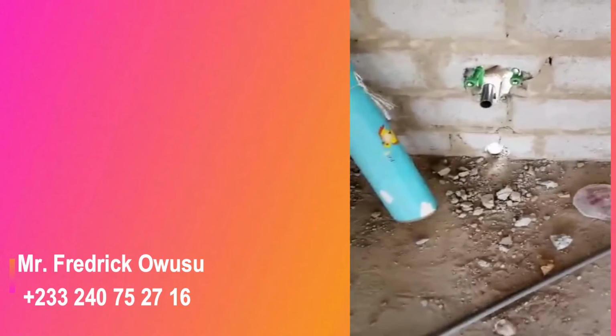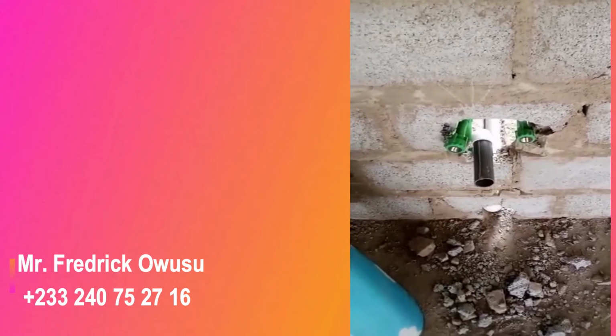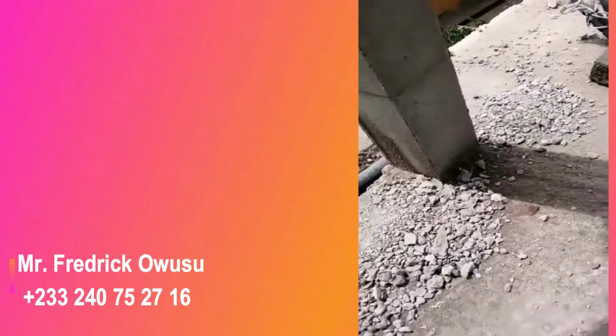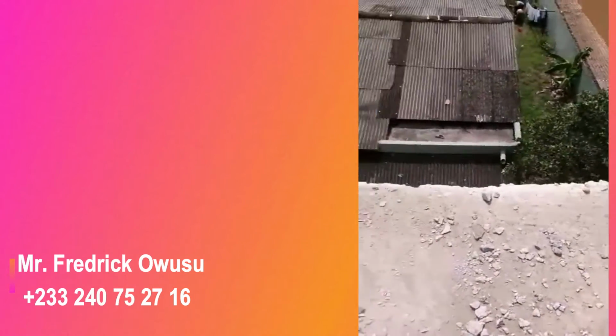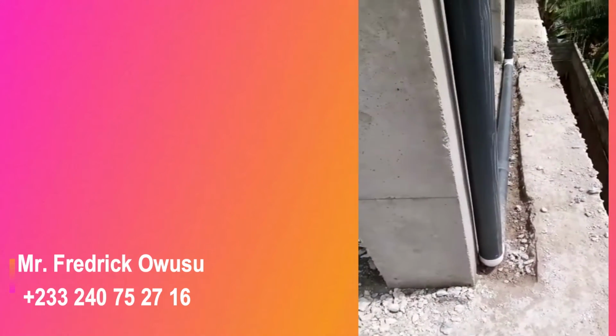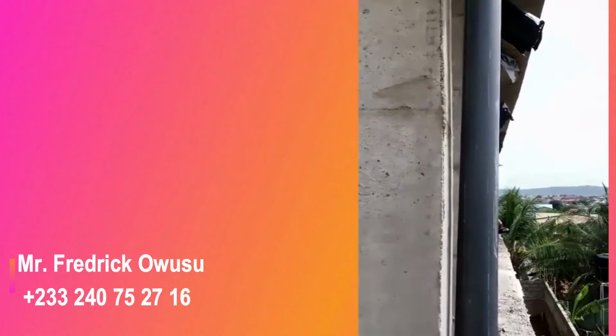Okay, yes, fitted and positioned so that in the near future you don't have to be coming back and chiseling the wall because there's a mistake somewhere. Make sure that if pipes are open and exposed, they put end caps on all those pipes. Because when plastering begins, some masons don't care. They can do their plastering and mortar will enter those pipes, and then you'll never know because it will sink down beneath the pipe.